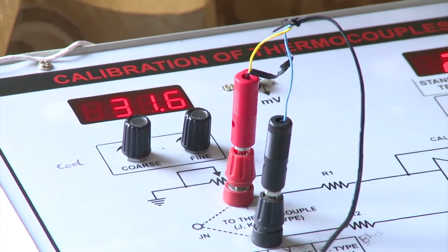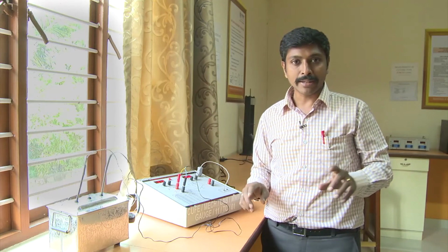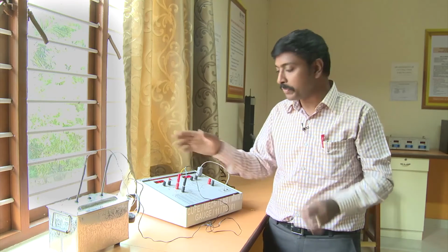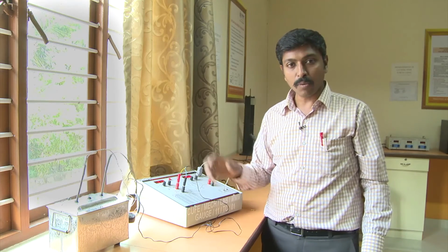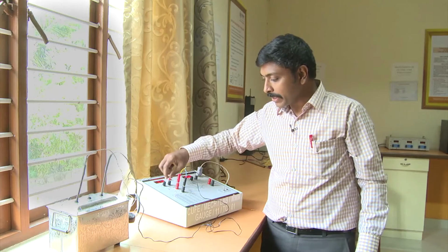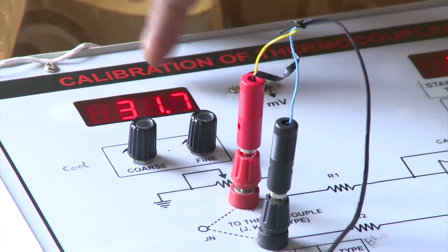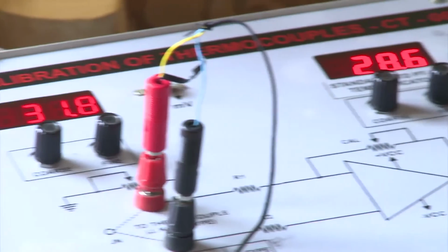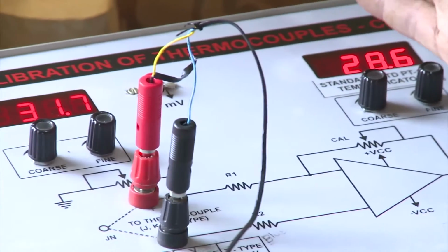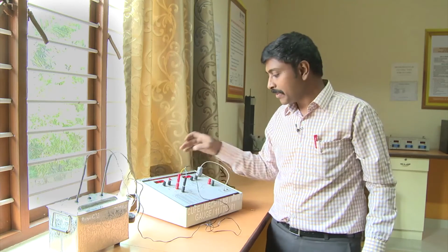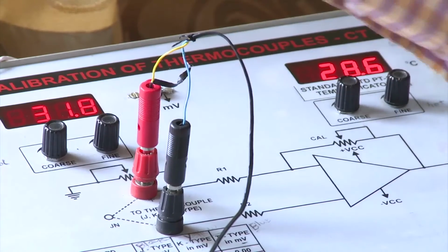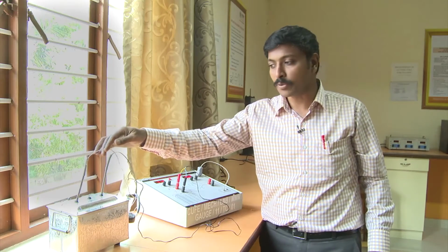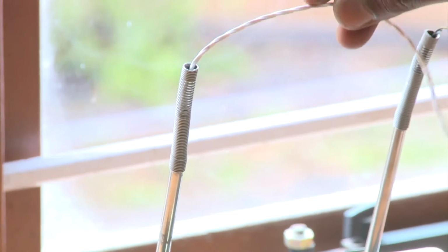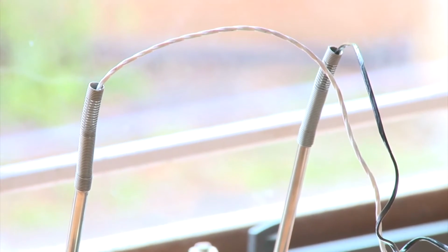That means you have to start the values from the same origin. When you plot the graph, both values have to start from the same point. So what we have to do is adjust these two knobs and reduce the value so that both displays will have the same value. Say for example, the right side is showing 28.6 degrees for water kept at room temperature, whereas the left side display is saying 31.8. I have told you that the right side equipment will not lie at any point. The white wire which has the RTD equipment inside will not have any chance of biased value.